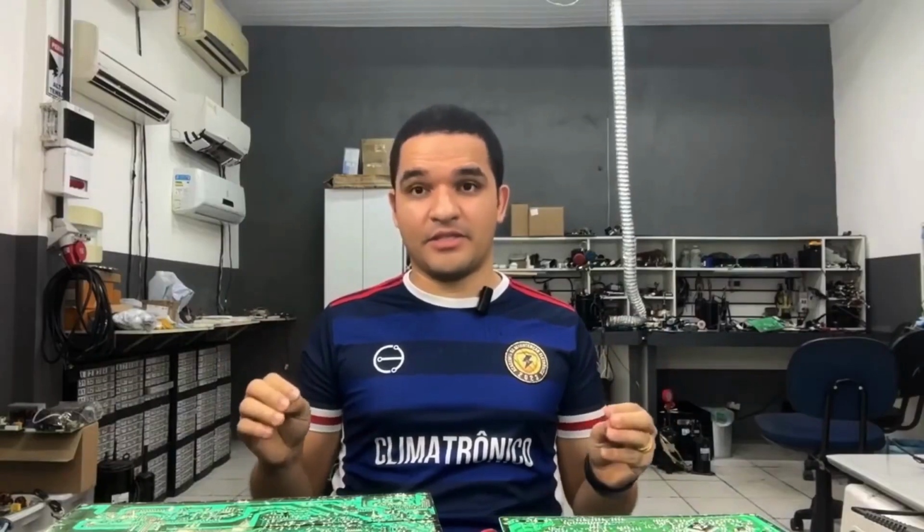Alternatively, it might be that there is indeed voltage present. In my experience, the majority of cases tend to be like this. There is voltage. There are 310 volts present, which is correct. However, the machine stops working and shows a DC link error, indicating a DC voltage problem. The voltage supplied to the board isn't enough. When this situation arises, which is the second hypothesis I am presenting to you, you will need to thoroughly examine the circuit that is responsible for accurately reading the voltage.